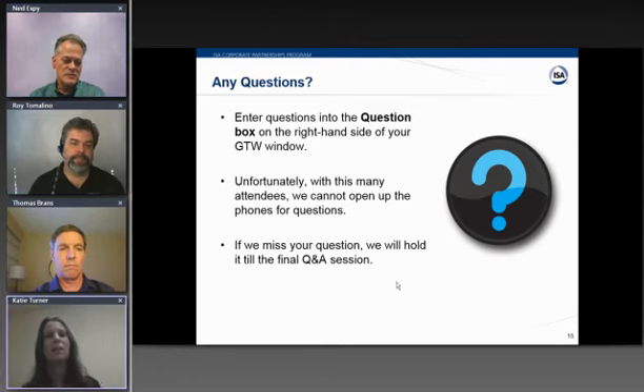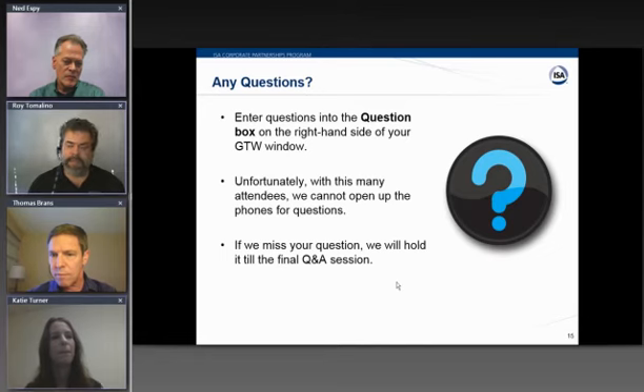Okay, we got a couple more comments from the person that asked that question. BMS stands for Building Management System. And as a follow-up question, he says, so the calibration tool does not have an interface port, am I right? So I think he might be talking about uploading it into the software directly. So when I get done with this calibration using the MC6 and the dry block, the data will be on the calibrator, and I can unload it directly into some calibration software without using a pen and paper. So that will all be automatic if that's what you're getting at.